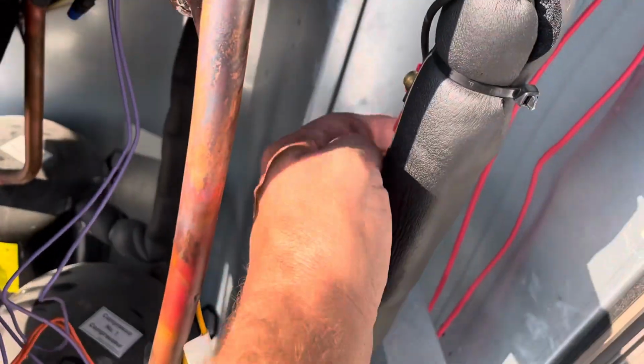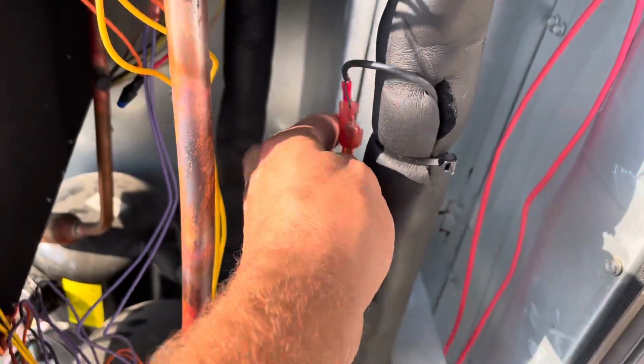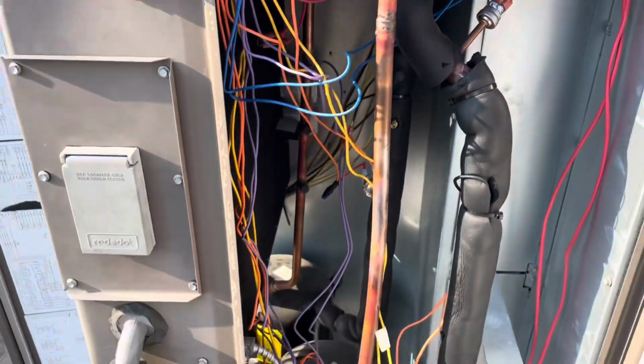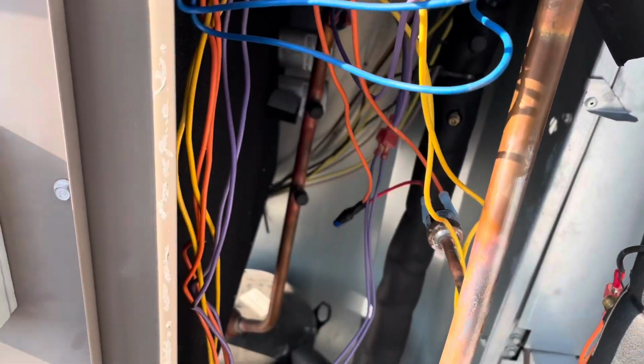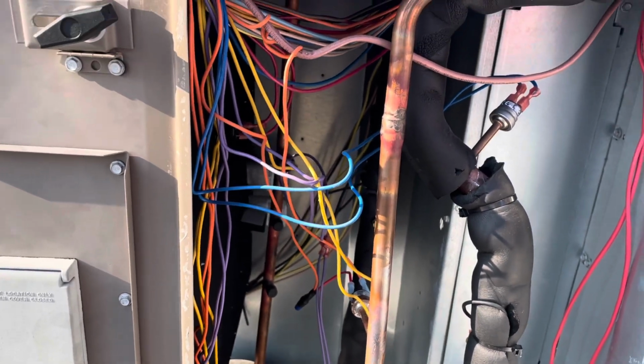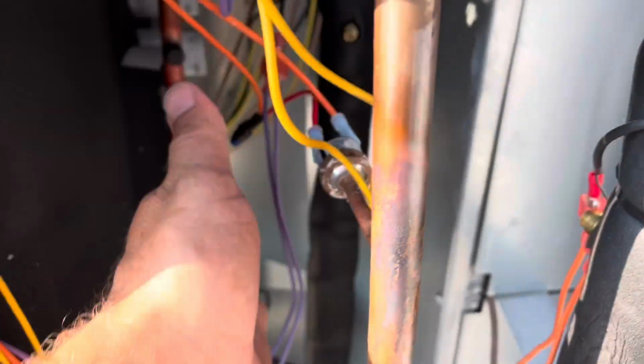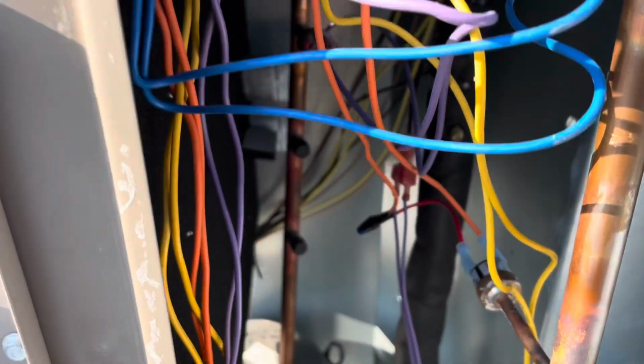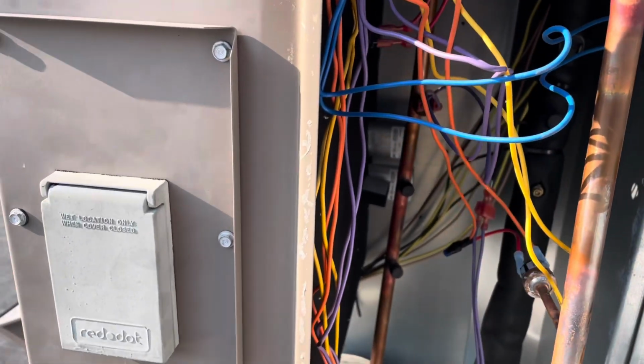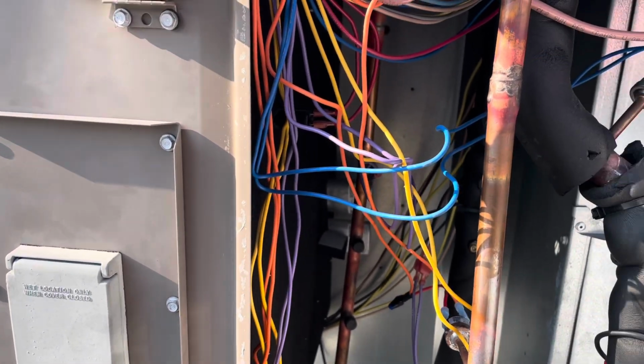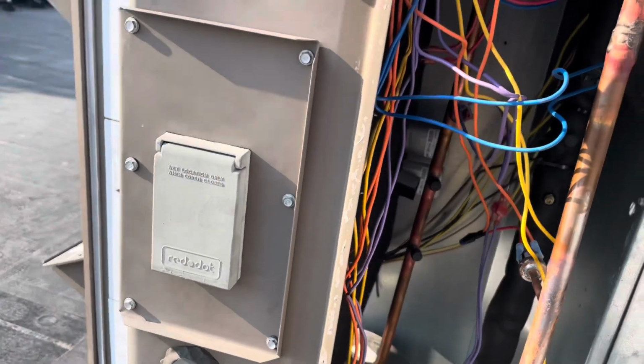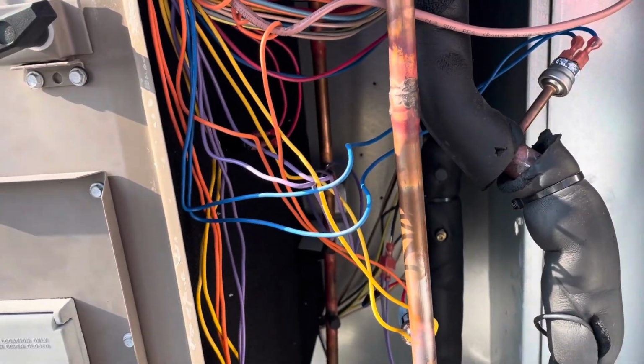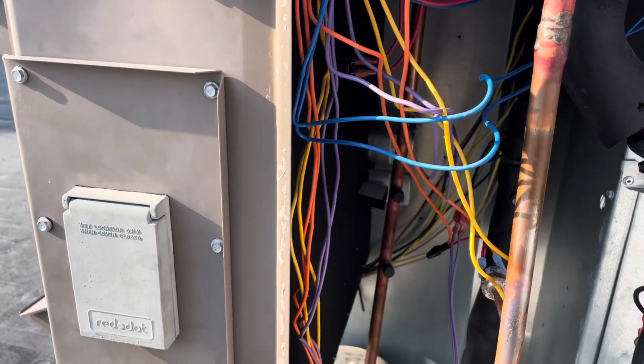All right, so I went ahead and fixed this sensor here, but started it back up to see what errors cleared, and I still had a compressor 2 shutdown due to low pressure. So I've lost all my refrigerant out of compressor circuit number 2. So I bypassed it for now and disabled compressor number 2 to get things going, to see if there's anything else before I really dig into this. Looks like I'm looking for a leak on compressor number 2, bare minimum.